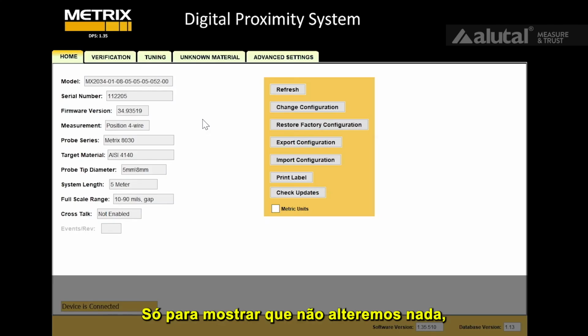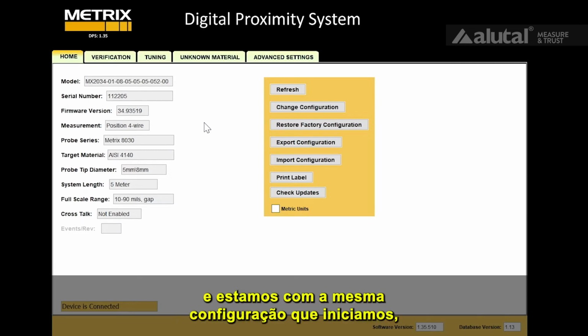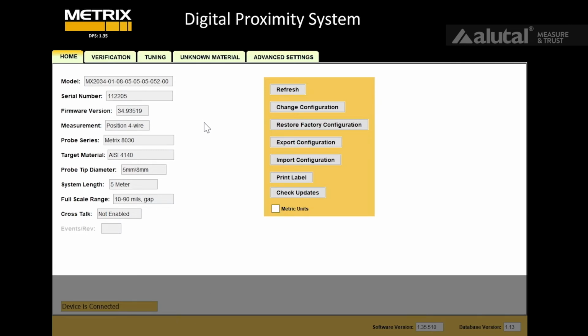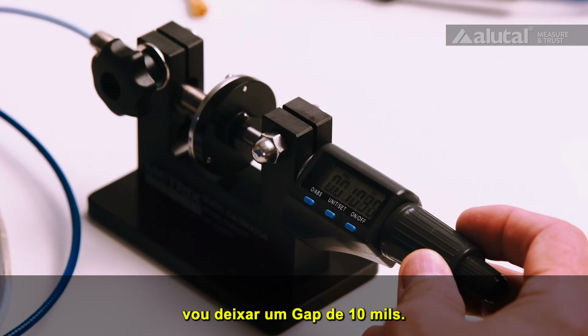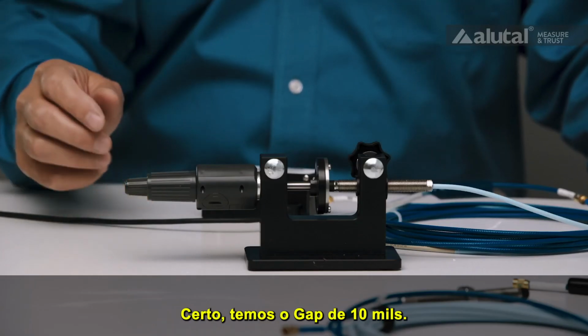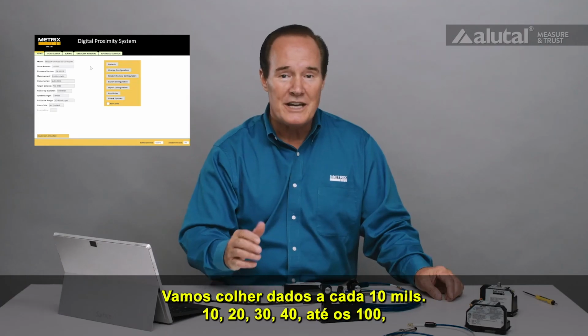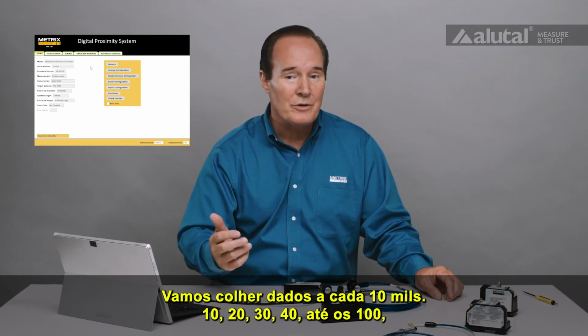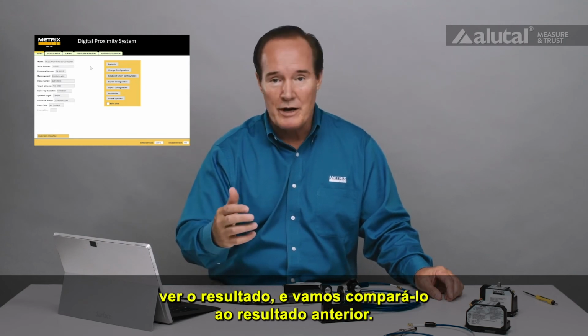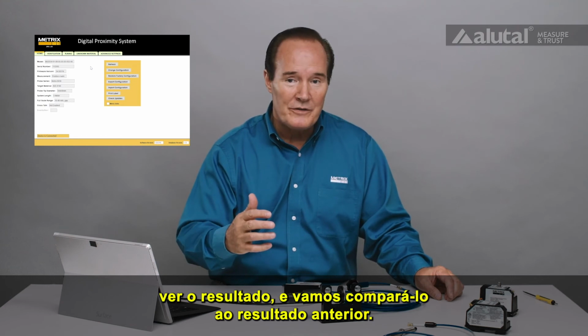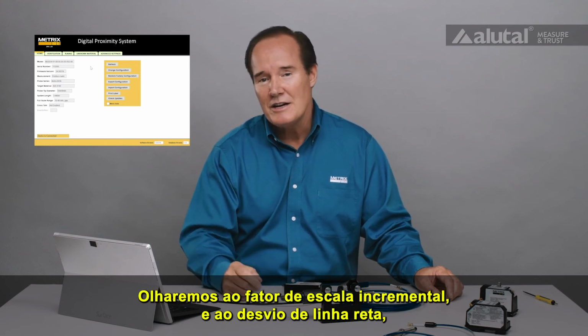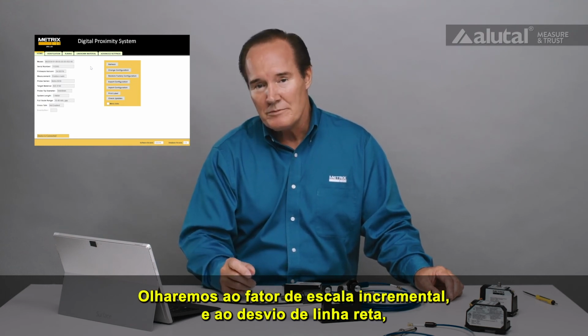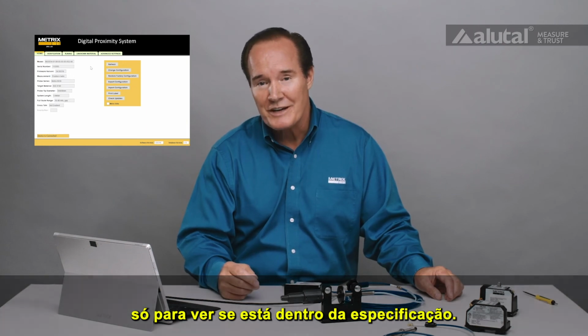Just to show you that we're still the way we were before, still the same configuration we started with, I'm going to go ahead and gap this to 10 mils. All right, we're gapped at 10 mils, so we'll take data every 10 mils, 10, 20, 30, 40, out to 100. We'll see how it looks, and we'll compare that to how we've done previously. We'll look at the incremental scale factor and the deviation from straight line, just to see if it's within specification.